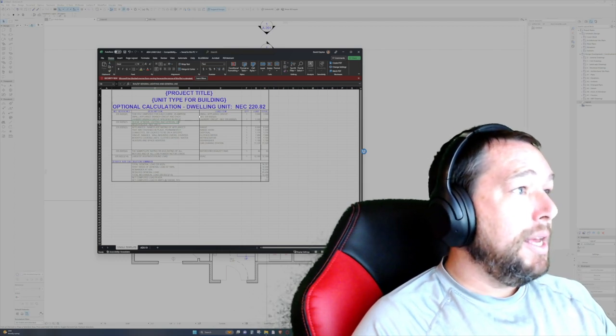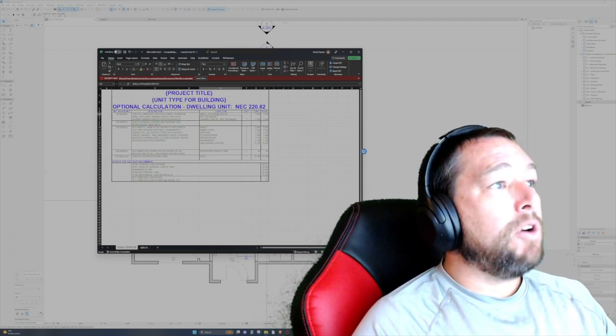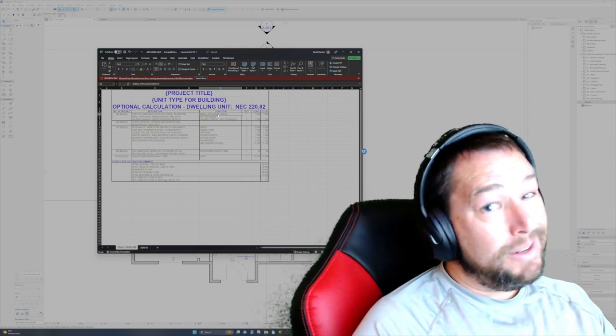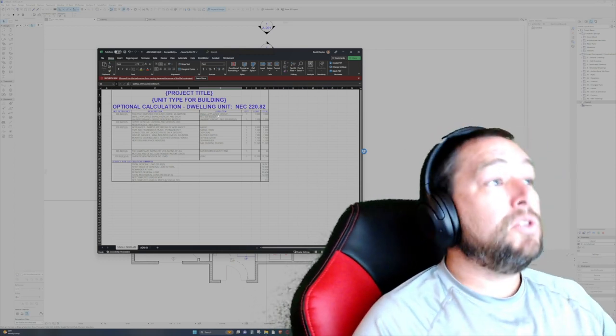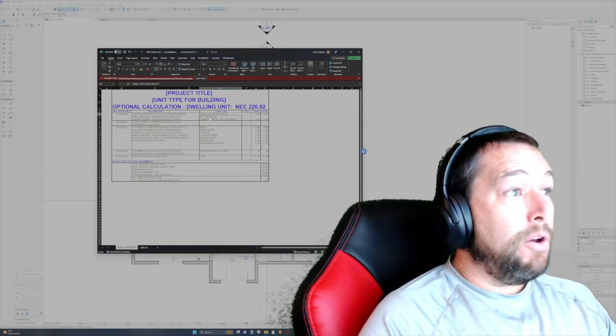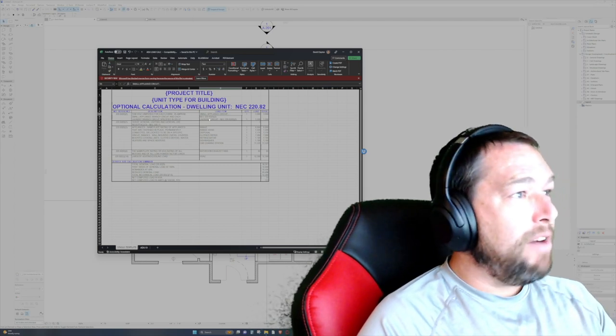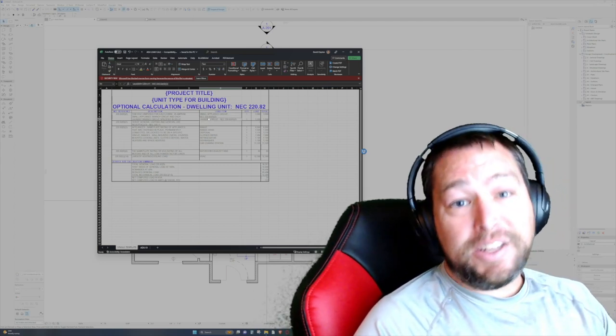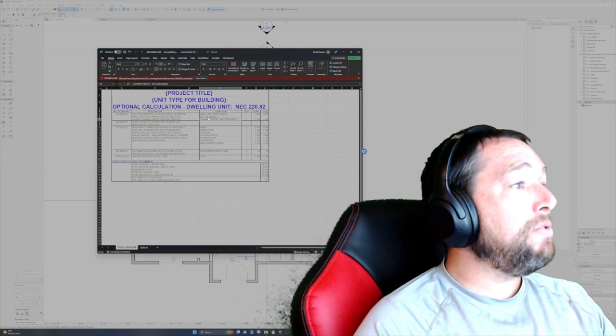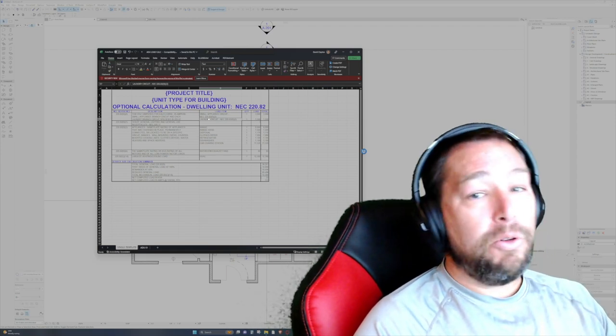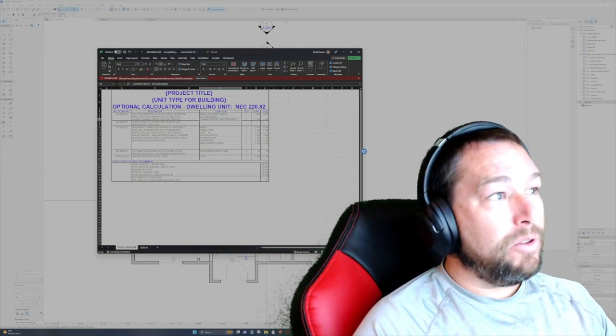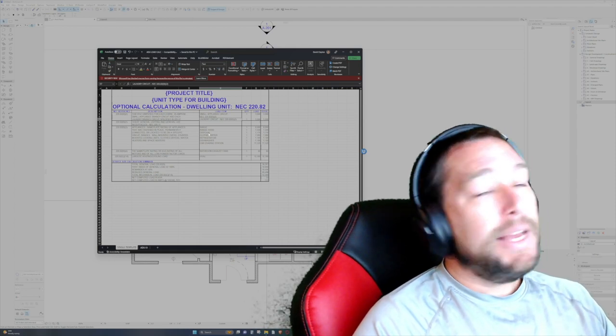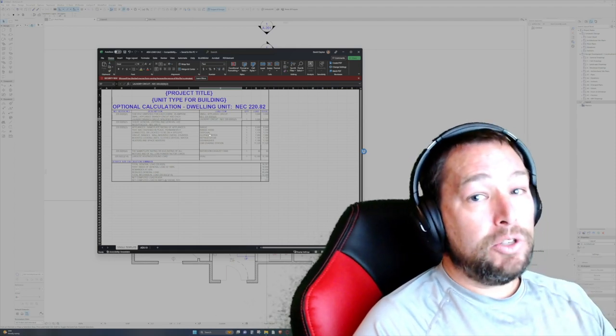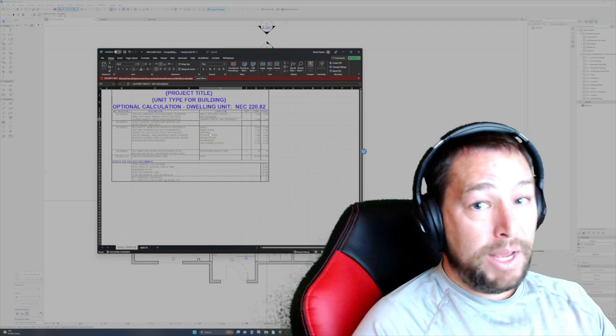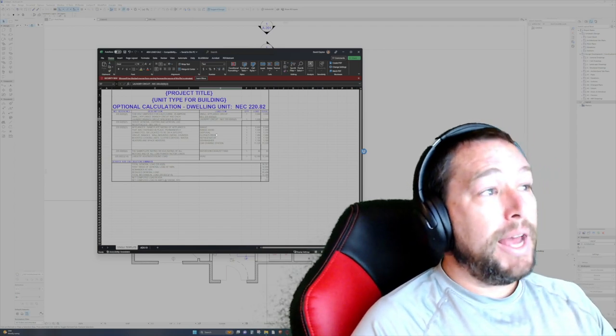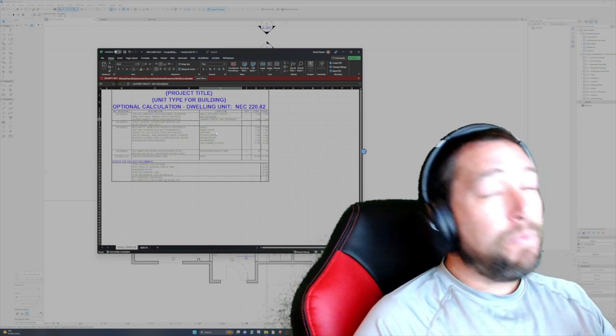As you can see, we've got our general lighting and general use receptacles at 3 volt-amps per square foot, and we also have our small appliance circuits. This covers the kitchen counters, things like the air fryer, and the laundry circuit. The laundry circuit typically refers to the clothes washer, not the clothes dryer. The clothes dryer usually takes a much larger electrical load unless you're using a natural gas powered dryer, but those are pretty rare.